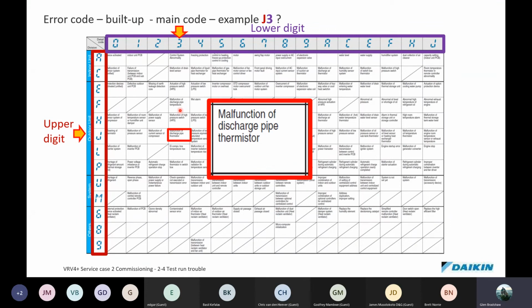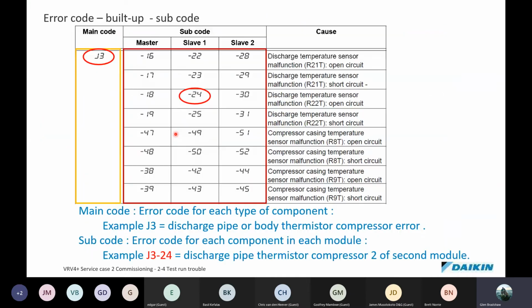Okay, so there we have a J3. Here's a malfunction of a discharge pipe thermistor. Over here, the thermistor has moved outside of the parameters. Okay, and there we see the system's error buildup with VRV4. We didn't just get a J3 error, we start to see some additional codes along with it. And these codes will point us in a direction.